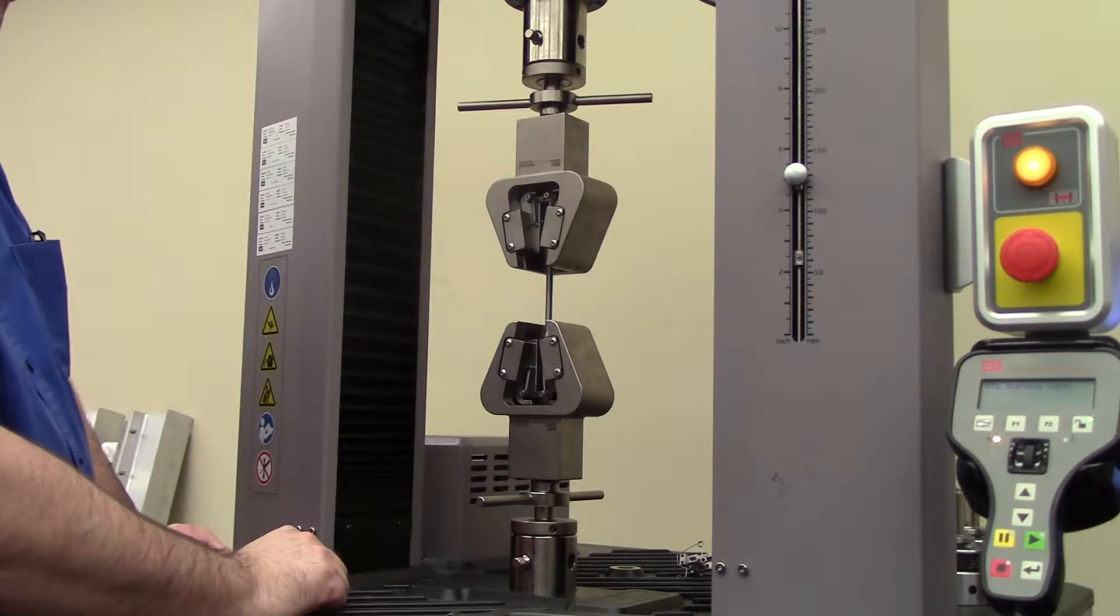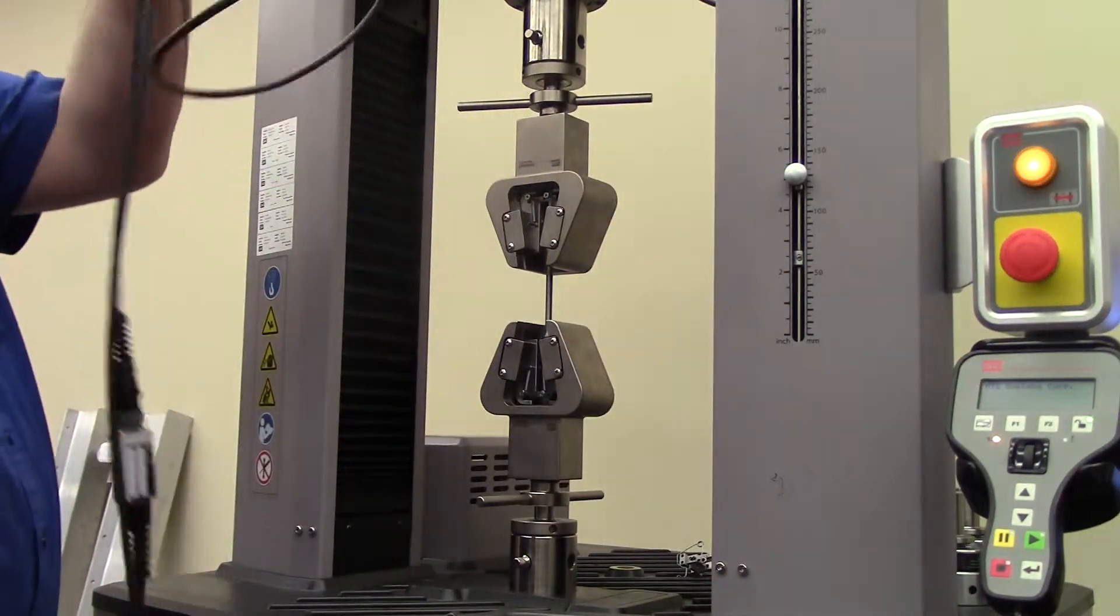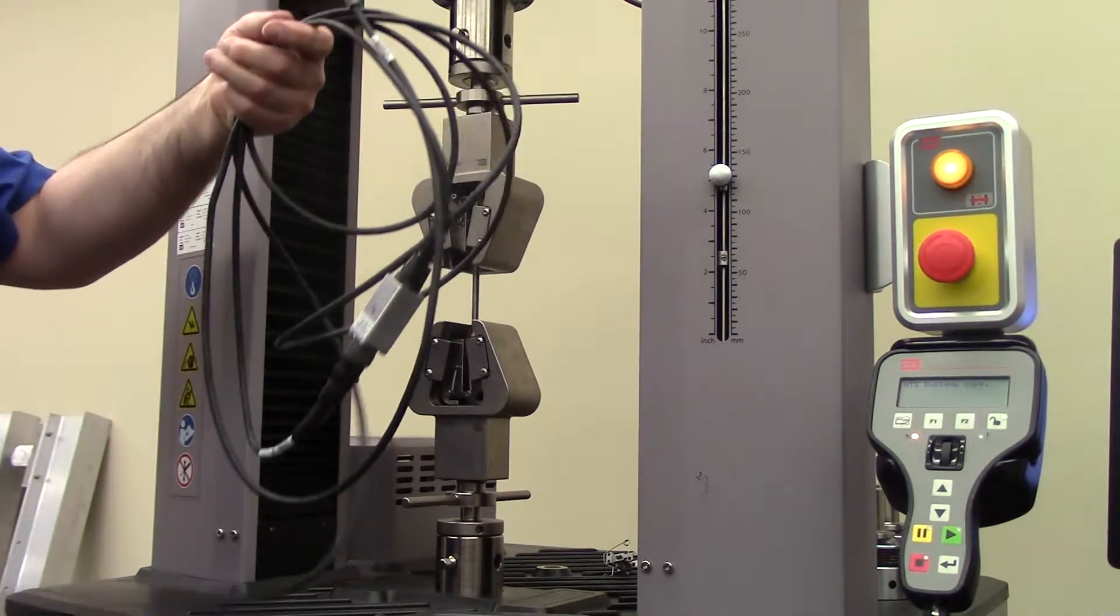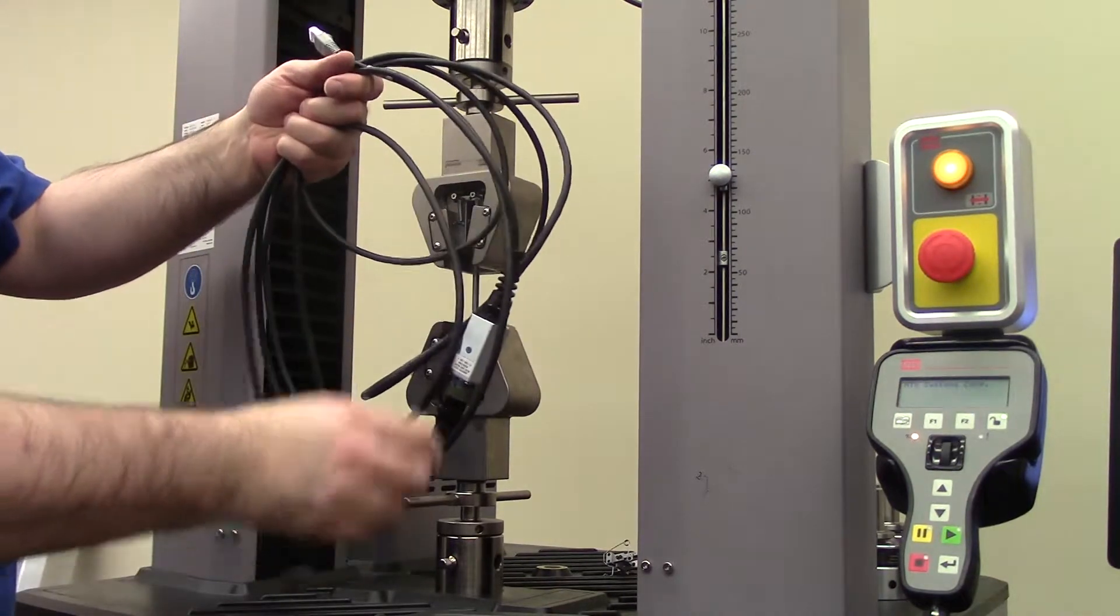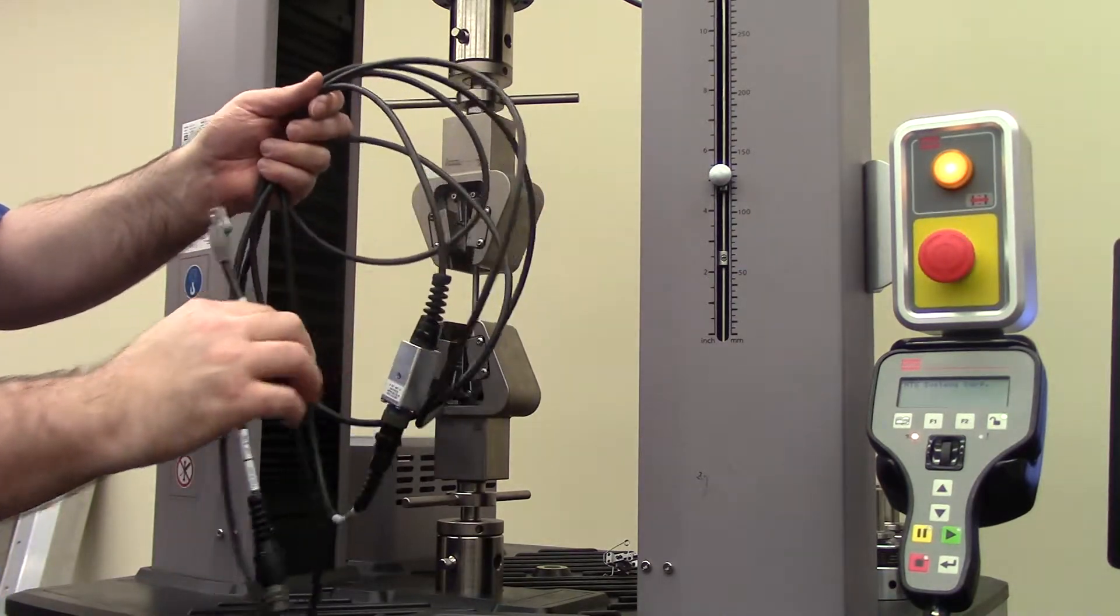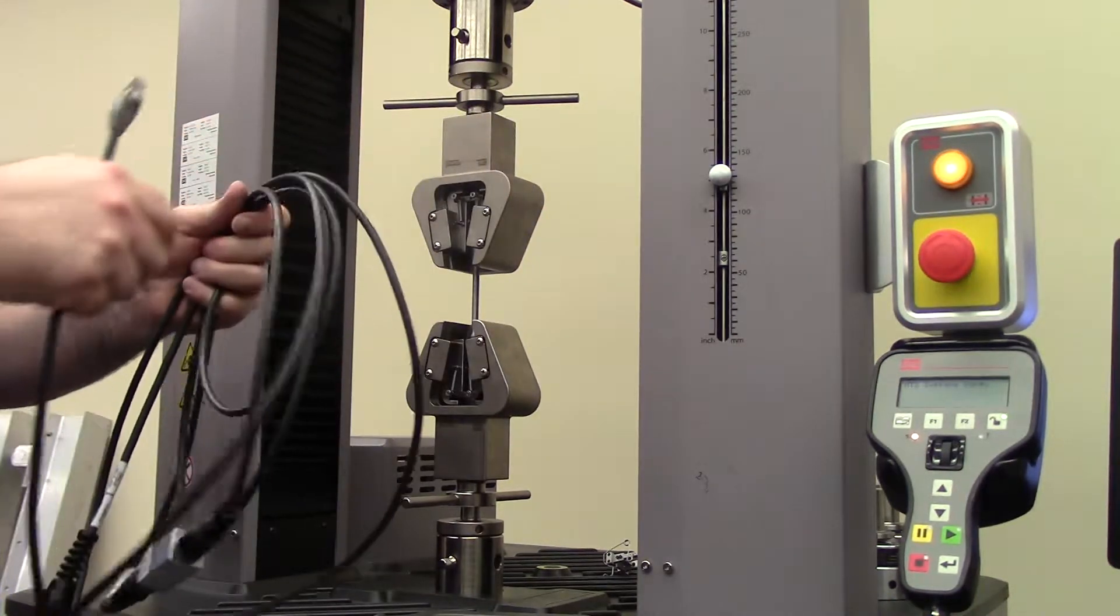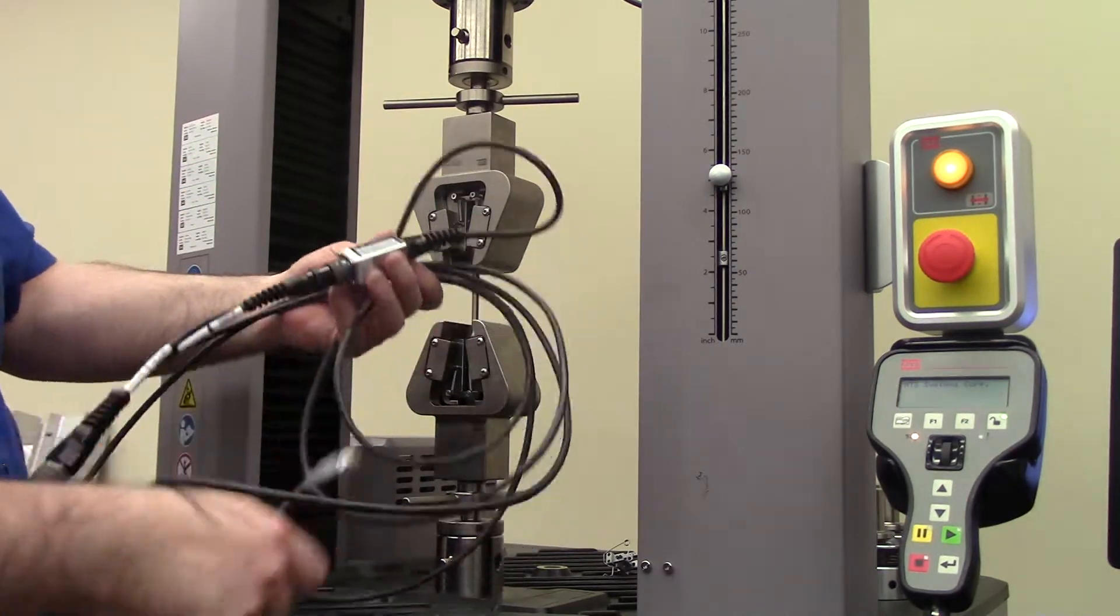Here's our extensometer cable. You notice it's not plugged in. There is a port on the side of the testing machine for the extensometer cable, and it's a touch cable so it's got this adapter on it.